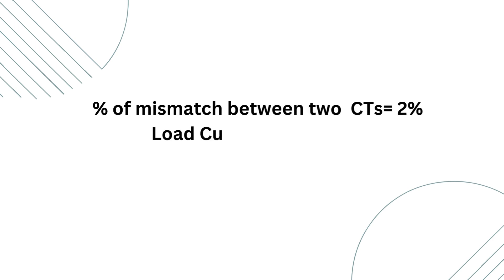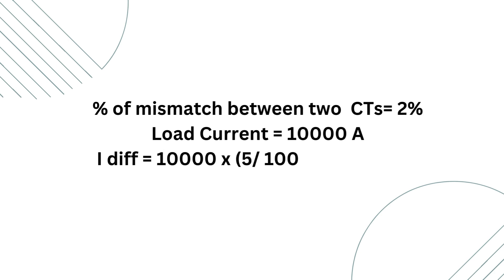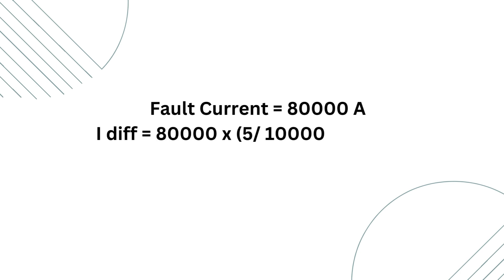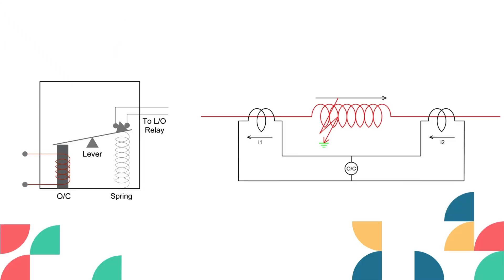Let's take an example. The percentage mismatch between two CTs is 2%. For a maximum load current of 10 kilo-ampere, we multiply 10 kA by the CT ratio (5/10000) and by 2/100 to get the 2% value — the result is 0.1 ampere, which is less than the set value of 0.5 ampere. But if the fault current is 80 kilo-ampere, the differential current will be 0.8 ampere, which can cause the differential relay to make the trip contact. We need the differential relay only for internal faults — for external faults, there are dedicated relays with different logic. So we need to ensure the differential relay only acts for internal faults, not external faults.